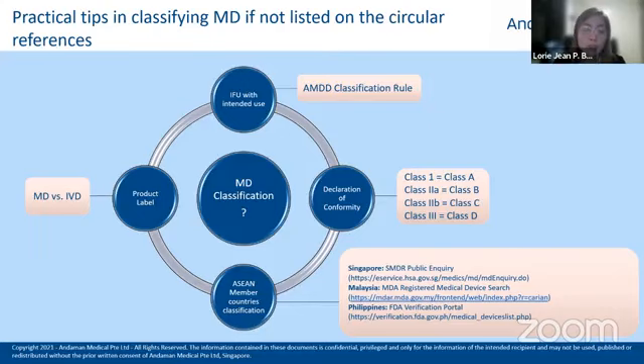Second one, we also refer to the declaration of conformity. The declaration of conformity usually contains the classification of the device. In the other countries, these are the classifications. If it's class 1, it's equivalent to class A for ASEAN. Class 2A, equivalent to class B. Class 2B, equivalent to class C, and class 3 is equivalent to class D.